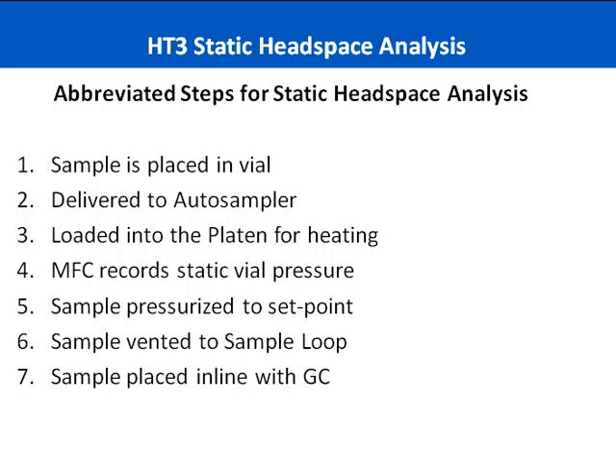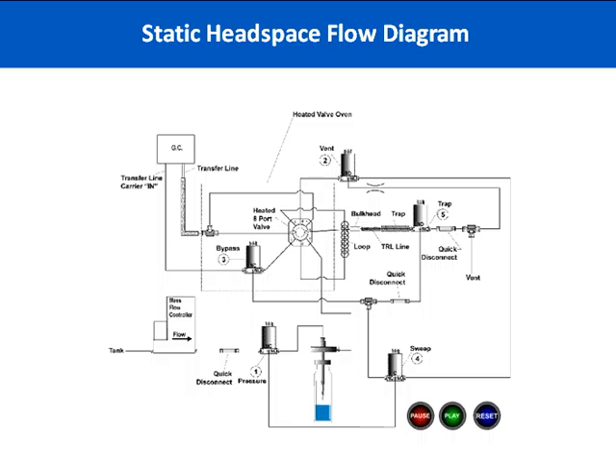With static headspace analysis, the sample is placed into a vial and sealed. That sample is then delivered to the autosampler, where it is loaded into a platen for heating. Upon reaching a final set heating time, it's then going to be mixed for a set period of time. Using our electronic mass flow controller, the static vial pressure is recorded, and that sample is pressurized to a user-defined set point. The sample is then vented through a fixed volume loop. The loop contains the sample at this point, and it's then valve actuated so that it can be placed in line with the GC column for separation and detection.